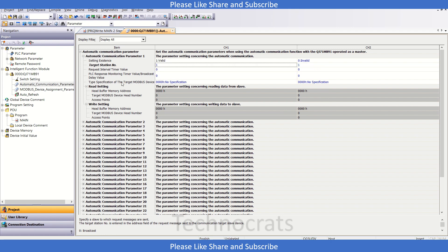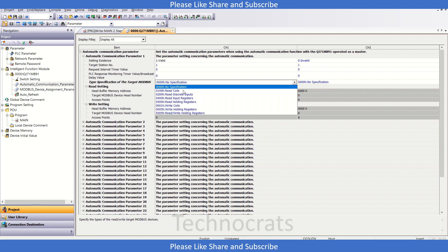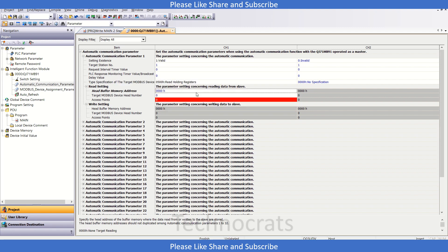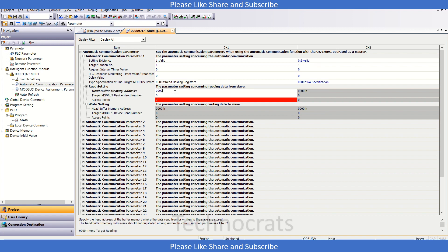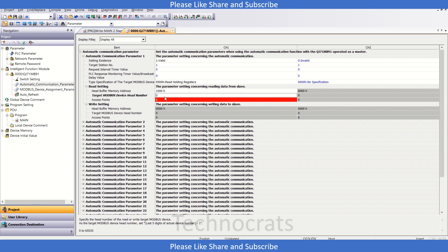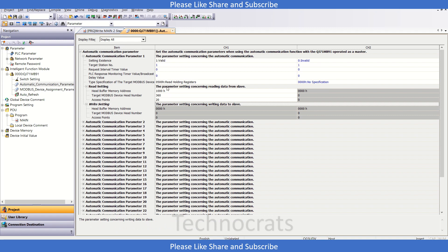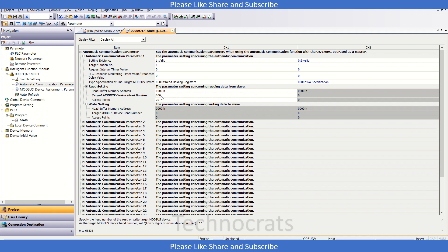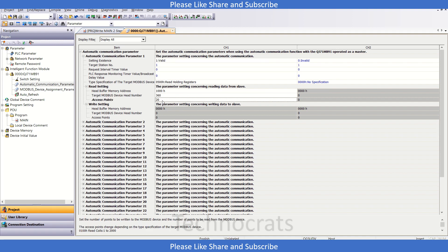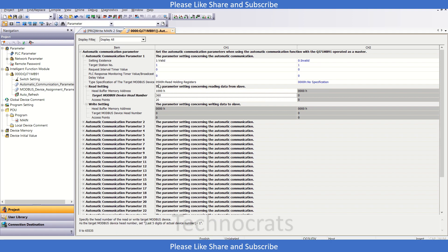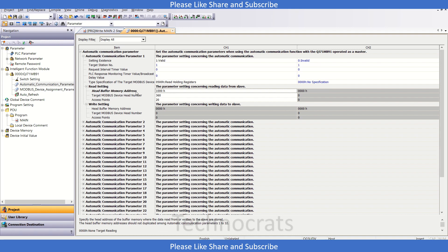After that, for the type of specification, let's use read holding register. To read the holding register, I have 1000 as my head buffer address, and the address which we want to read from the device is 360. We will read 20 words. This instruction means we will use 360 as the Modbus address and read 20 access points, starting from 360. It will be read holding register, and the head buffer address of my module will be 1000.